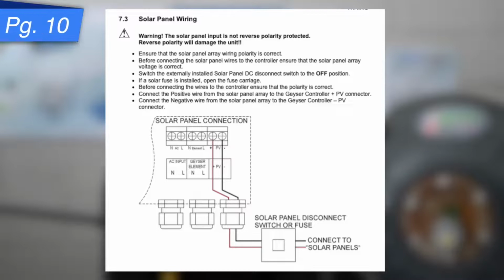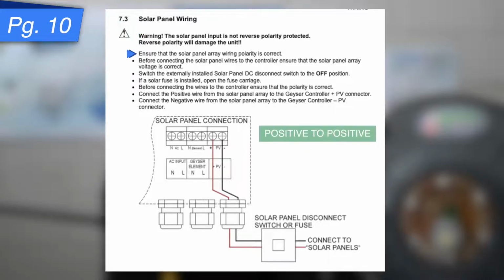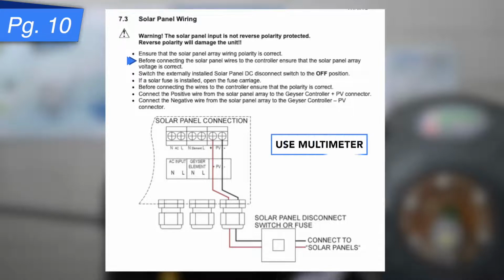Page 10 then indicates the solar panel wiring. Just important to note that it is not reverse polarity protected, so please make sure that you're connecting the positive to the positive and the negative to the negative, otherwise the unit will be damaged. Please make sure that the polarity is correct before you actually connect it, and you can do that by testing it with your multimeter.